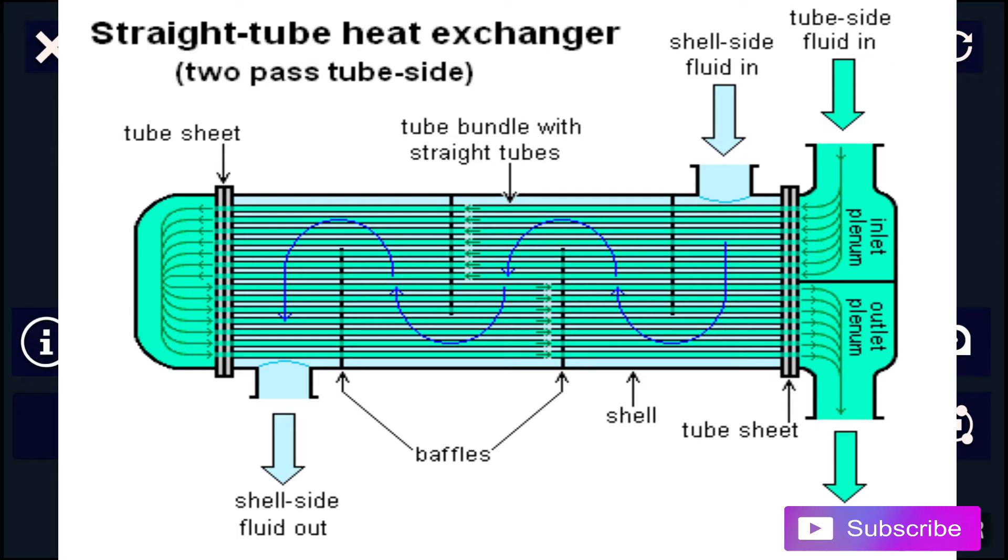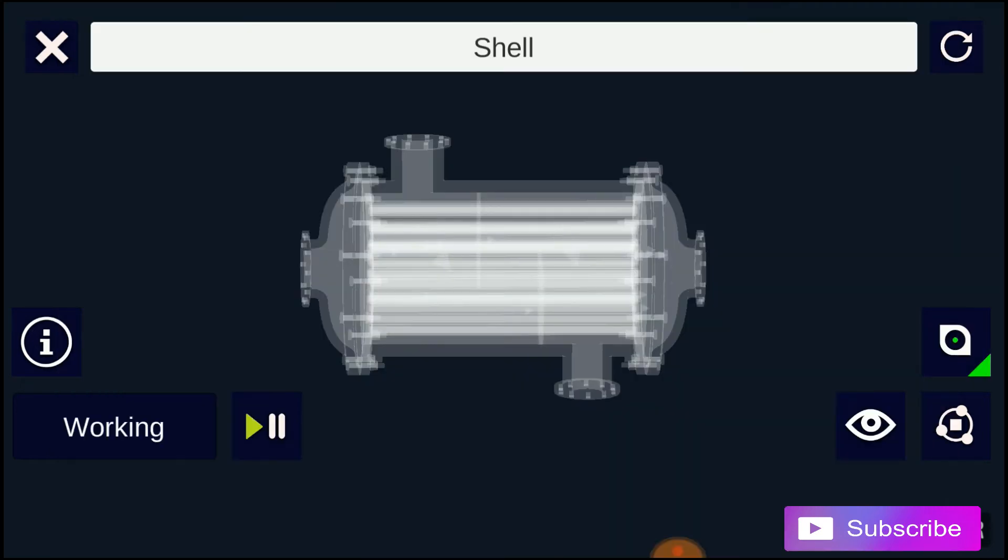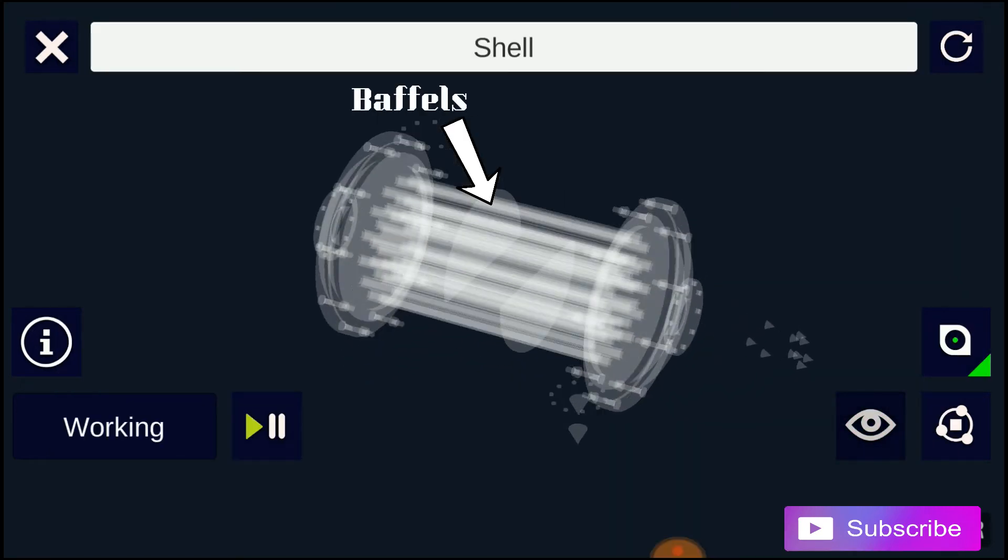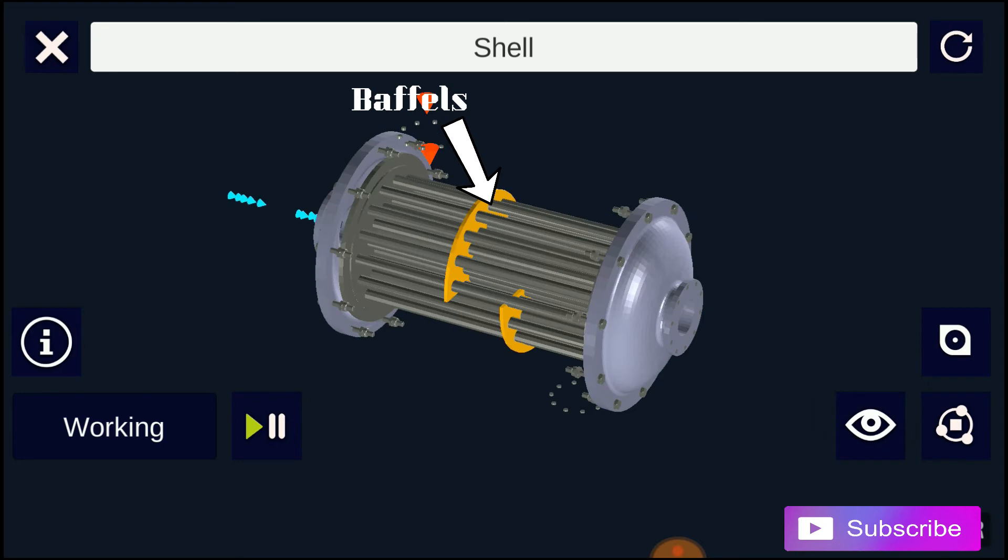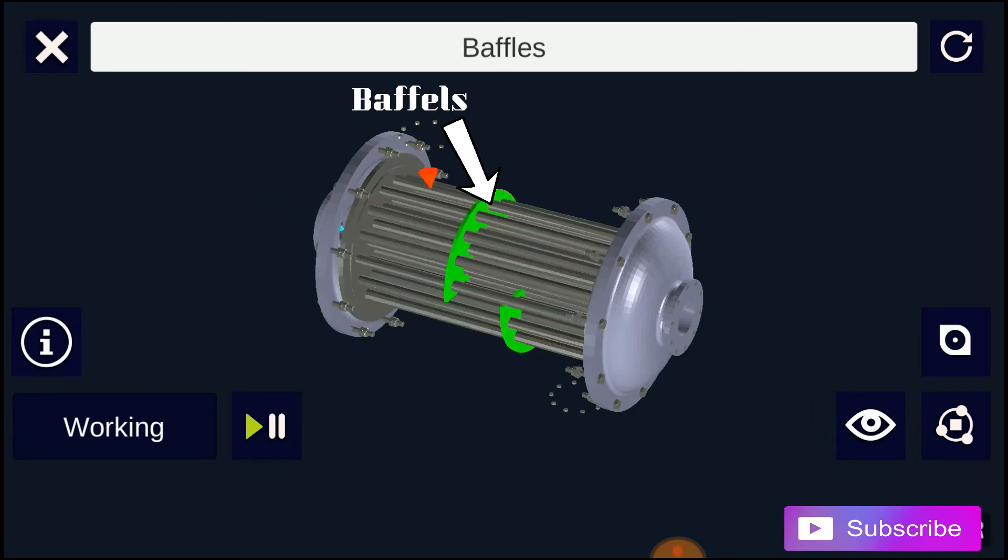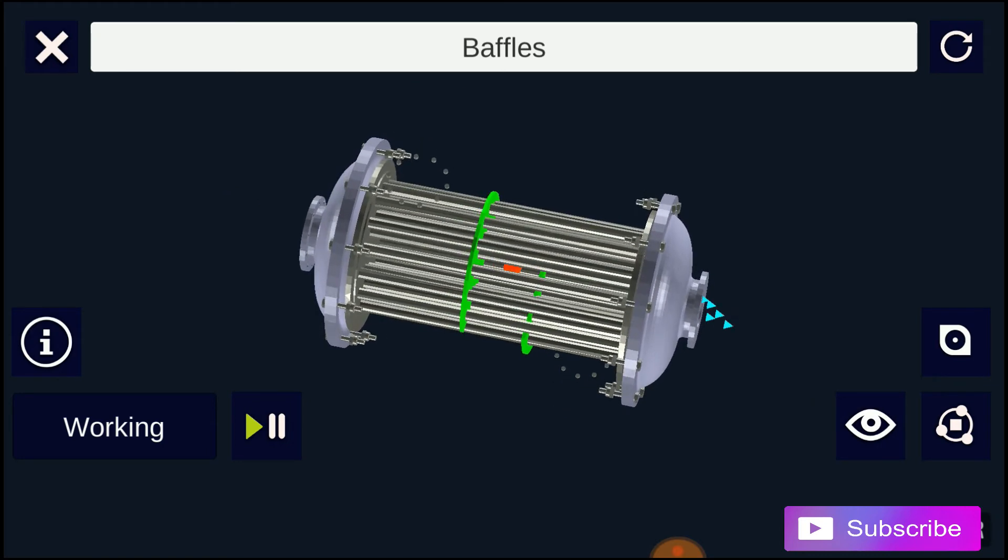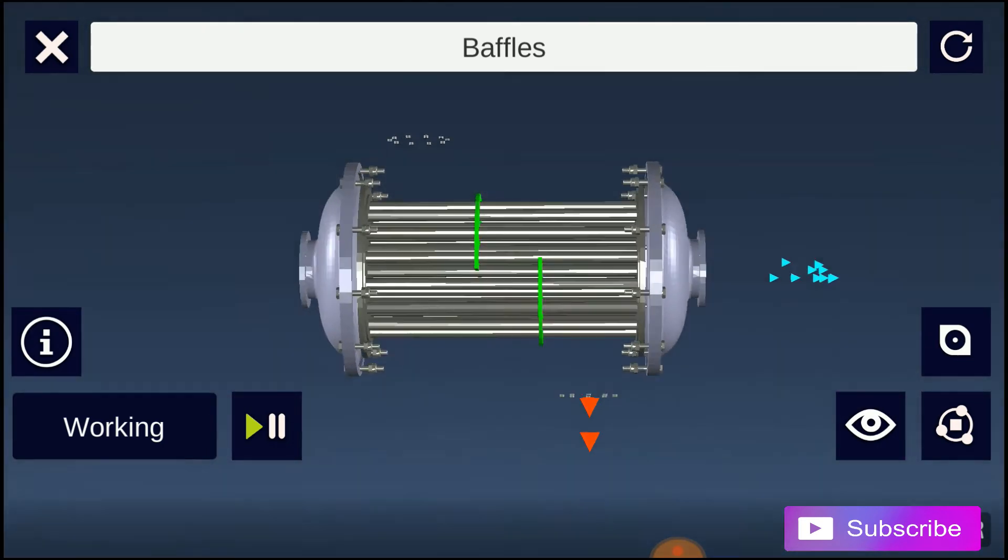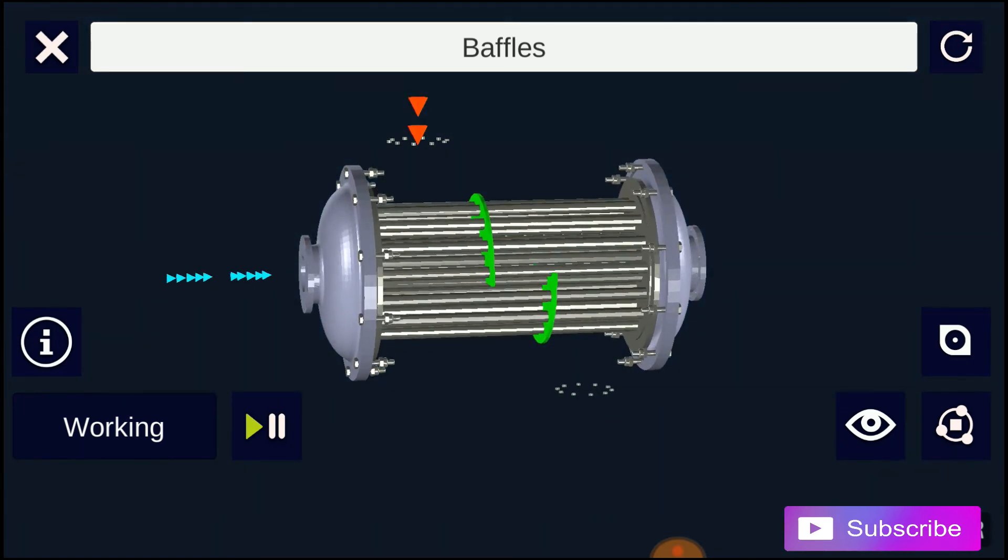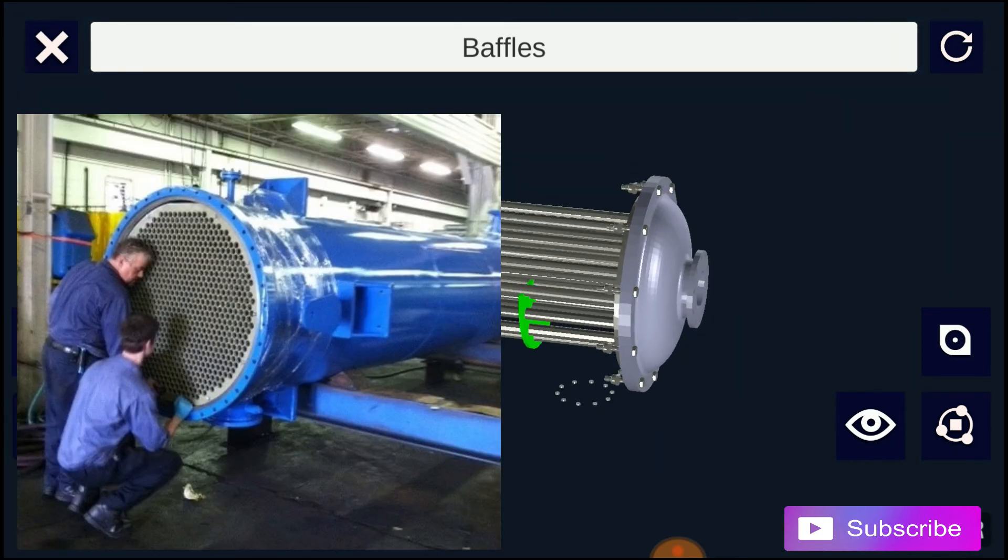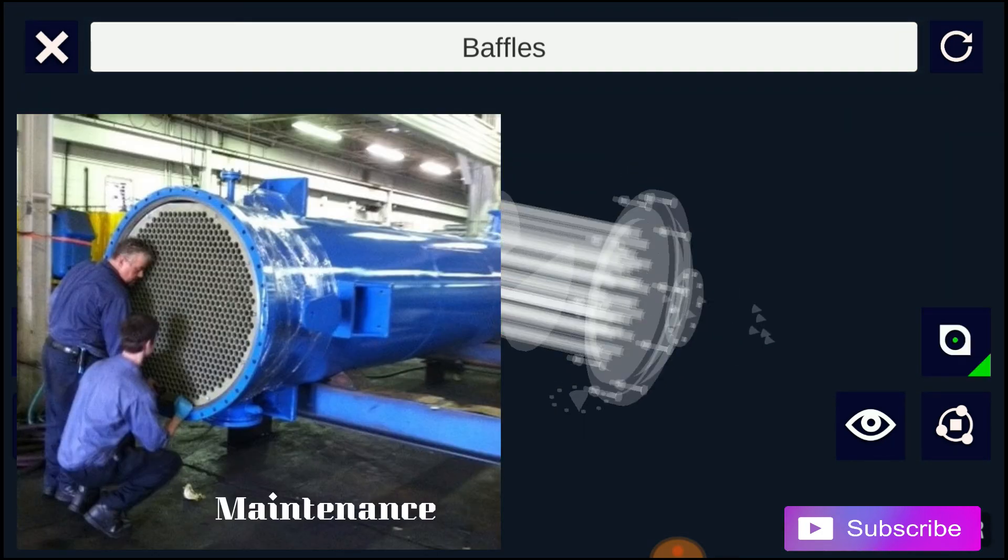There are often baffles directing flow through the shell side so the fluid does not take a shortcut through the shell side, leaving ineffective low-flow volumes. These are generally attached to the tube bundle rather than the shell in order that the bundle is still removable for maintenance.